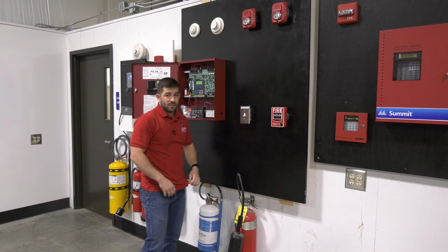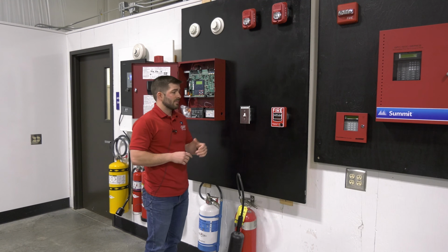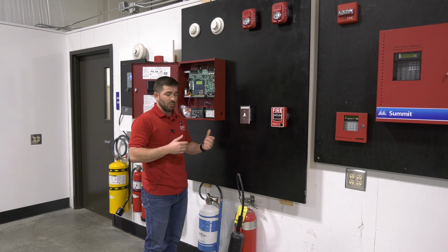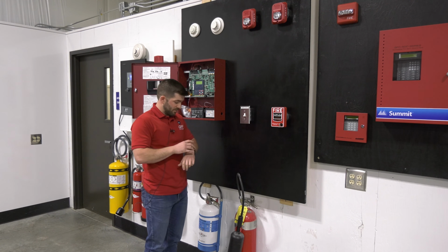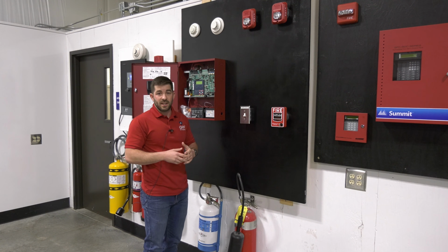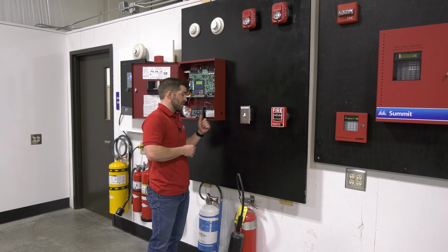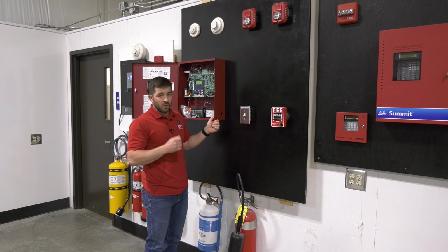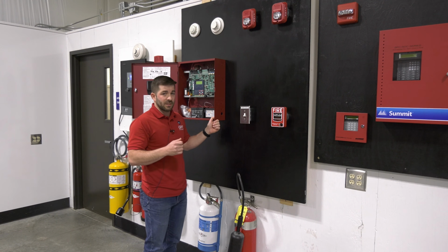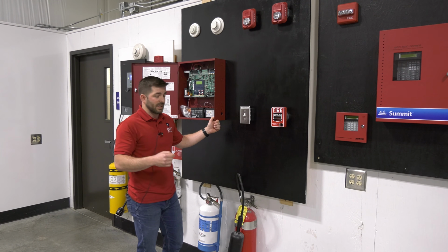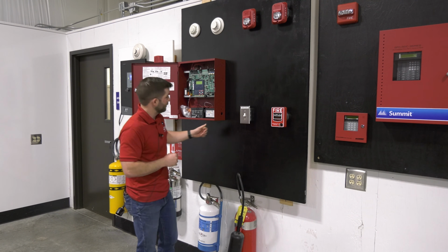Now, an alarm signal has up to 10 seconds, again, to enunciate the panel. And a lot of inspectors out there, especially when water's starting to flow, are checking their watch for 90 seconds for it to initiate a flow switch. Now, for a flow switch to initiate a fire alarm panel can actually take up to 100 seconds, because you've got 90 seconds for the water flow switch to initiate from water flow, and then an additional 10 seconds for it to initiate the panel.